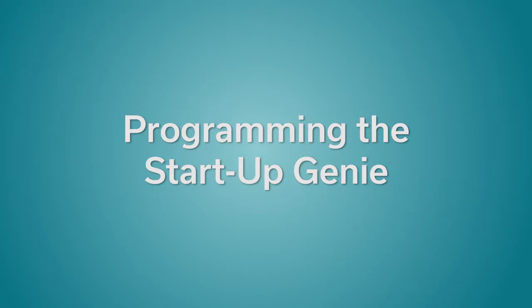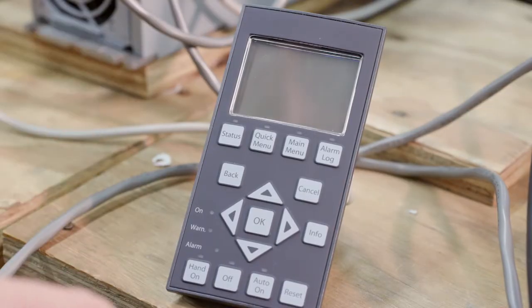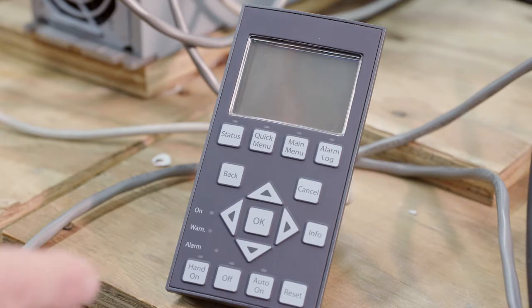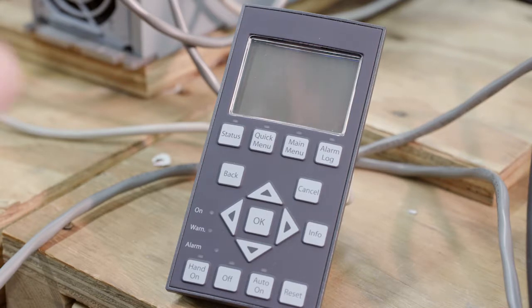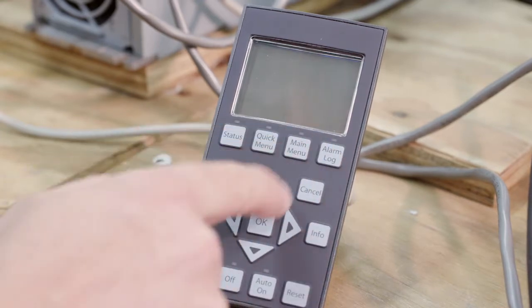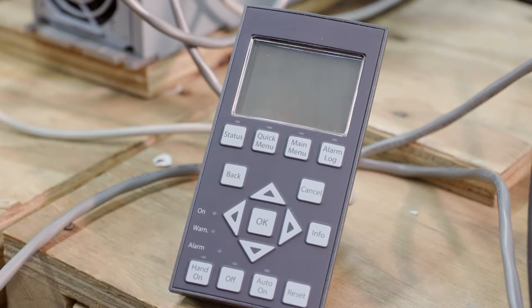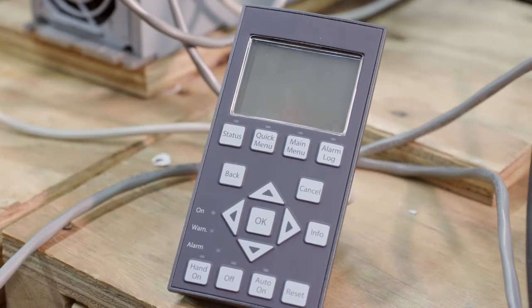Let's start off with an initialization or factory reset. The reason why we're going to do that here is because these are used for demonstration purposes. So let's just get everything back to the factory defaults. Now there's two ways to do that. One is turn the power off, press status, main, and OK. Those three buttons, hold those down, turn the power on, and keep those buttons pressed until you see initialization on the screen. Then you can let go. That's one way to do it.